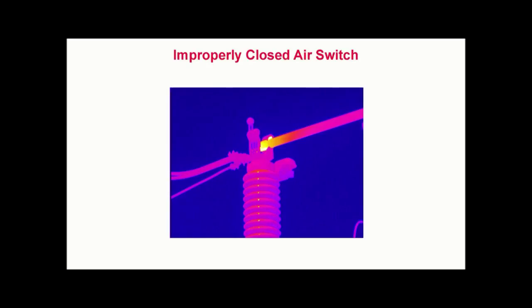If you look closely, you will see that the contact points on the switch arm are at the 7 and 1 o'clock positions rather than the 9 and 3 o'clock positions indicating that the switch arm had not rotated fully.